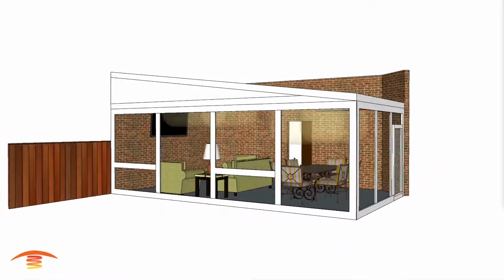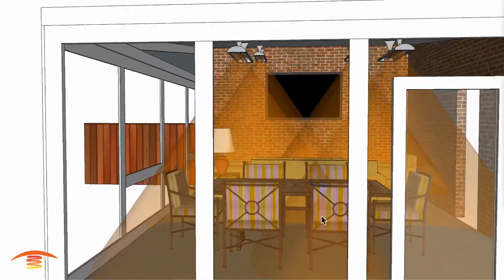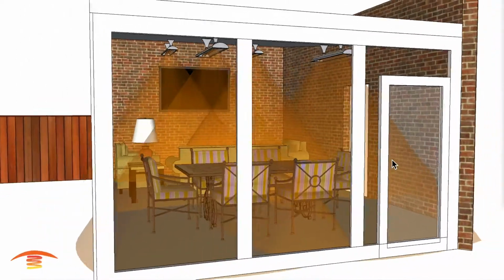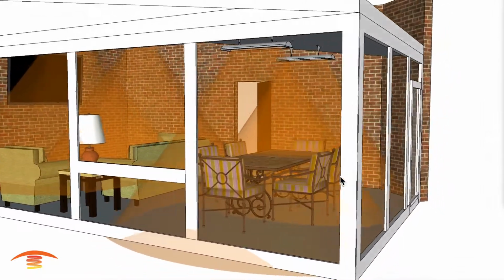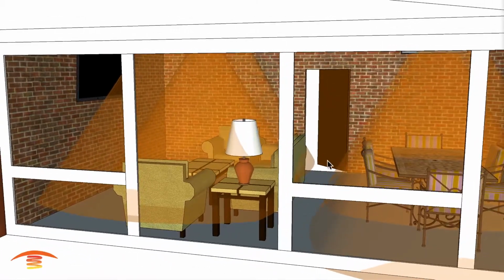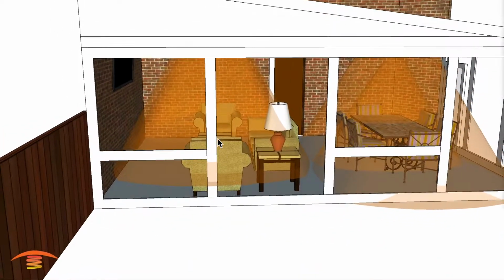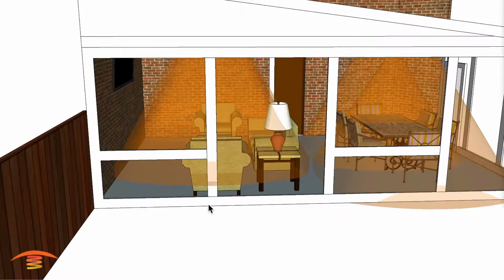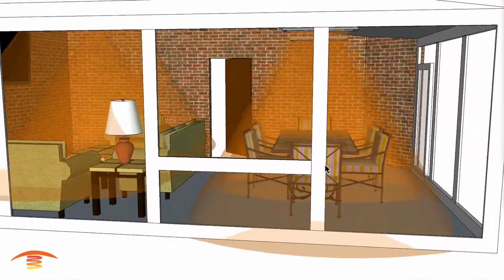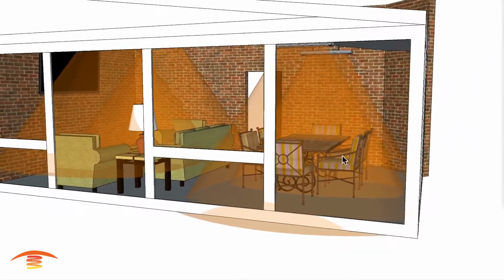All right, so let's go ahead and look at the footprint of heat with this application. So this is why I really like this. These 5,000 watt units are able to produce enough heat for this whole entire space here and this whole entire space over here. There is a small section that is not heated. Now you could move the heater down slightly, but I wanted to kind of keep it uniform as far as the position being centered here, centered there. And here you can see, again, everything is relatively very well heated over here as well.